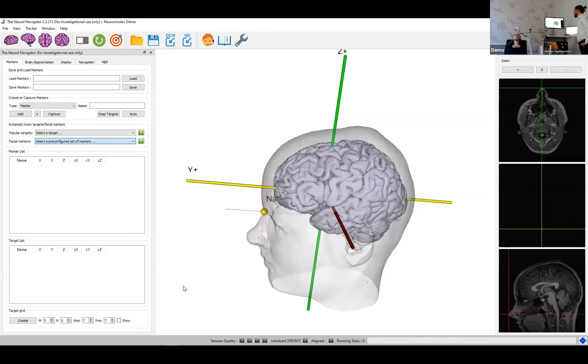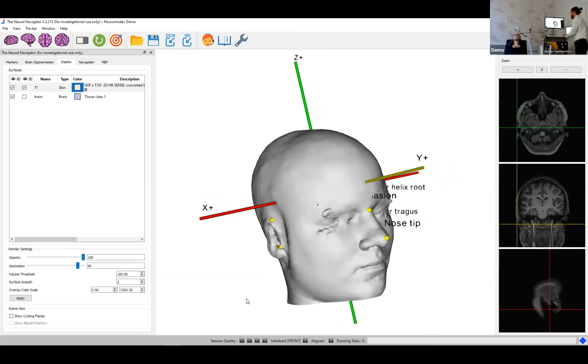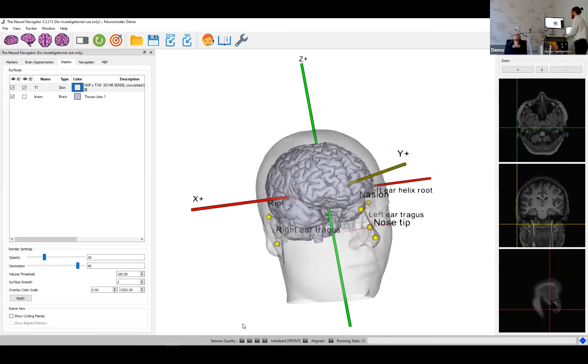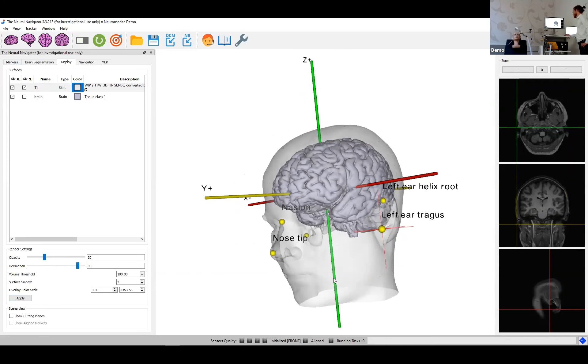Because this is a pre-configured set of markers, it's good to always manually check whether the markers have been placed correctly and adjust where needed. Those are already quite accurately placed. Placement of the markers is really a matter of personal preference. What's important is that the markers you place inside the MRI scan are positioned in a way that you can also easily identify them on your patient's head. That's why the nose tip is a clear anatomical feature, together with the nasion and aspects of the ear. But for example, the inion is harder to identify on the patient's head.